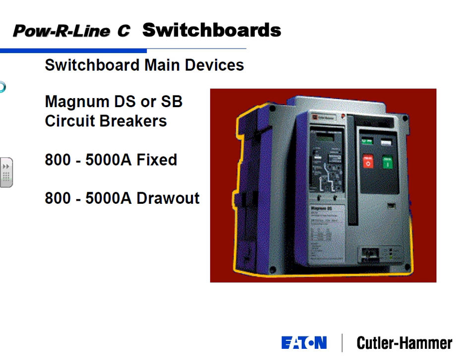So the Magnum SB is the switchboard breaker, which is designed only for a 3-cycle switchboard, and therefore it's not designed to sit there for 30 cycles. What are the trade-offs, or what are the benefits? It's a little better, it's more cost-effective. You're not going to misapply it, because you're not going to put a device that sits there for 30 cycles into a switchboard that would blow up in 30 cycles. Now, there's nothing preventing you from putting the DS circuit breaker in a switchboard. We do it commonly, it just has to be done under the right application.